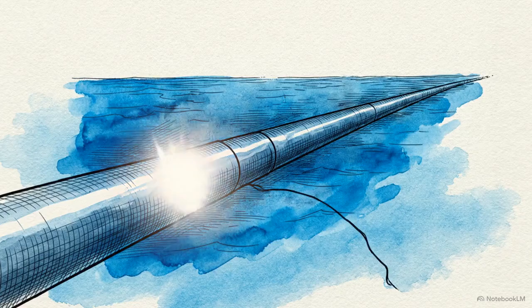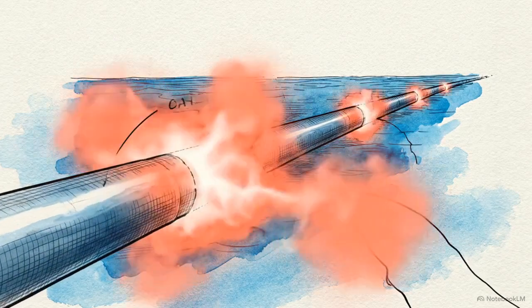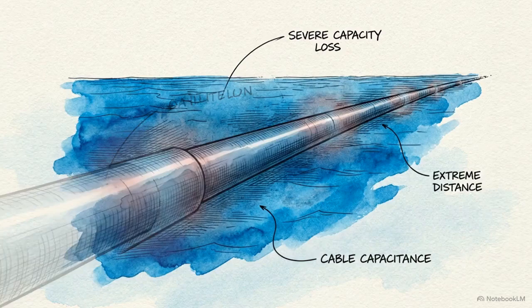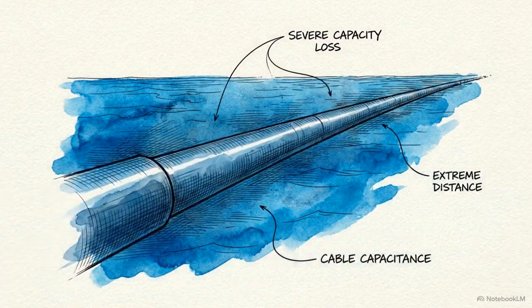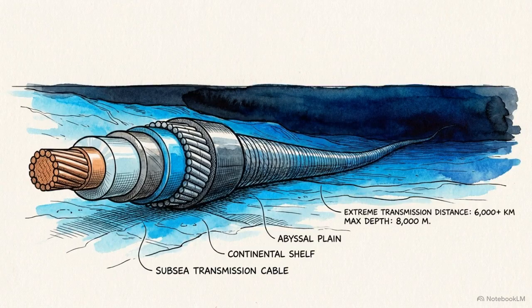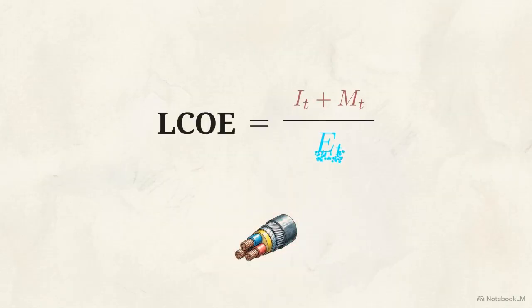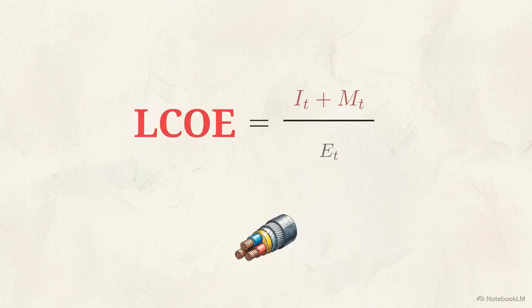For farms located close to land, high-voltage alternating current, or HVAC, is the standard transmission method. But as cables extend past 100 kilometers, alternating current begins to suffer severe capacity losses due to cable capacitance. If developers try to push alternating current over extreme distances, the resulting line losses strip away a massive portion of the denominator, effectively negating the offshore wind advantage.